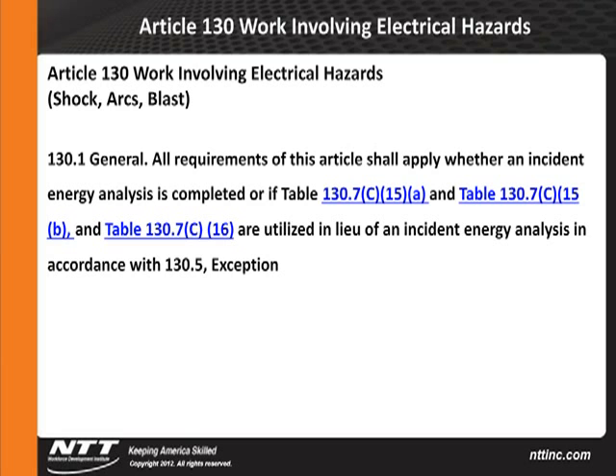If you haven't done a hazard risk analysis, your qualified employee who knows how to read, knows their job task, and knows their voltage can go into the set of tables, find the equipment, the voltage, and the task, and without doing an analysis, come in under hazard risk category and find the type of clothing that needs to be on their body. It'll indicate the minimum requirements: they need voltage-rated gloves and insulated hand tools.